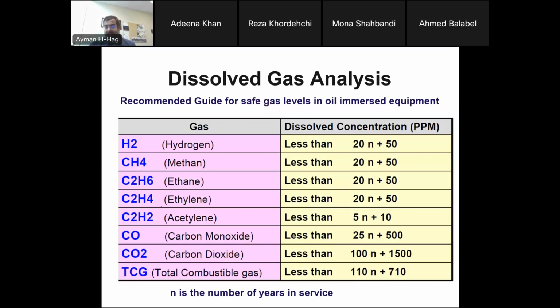And there is a recommended guide, again for all-age transformers, where N is the number of years in service. These are the gases we are looking for: H2, CH4 (methane), C2H6 (ethane), C2H4 (ethylene), C2H2 (acetylene), CO and CO2, and the total combustible gases. So these are some limits. For example, for H2 it's 20N plus 50, where N is the number of years in service. Let's say you have a 10-year-old transformer, so the recommended value is less than 20 times 10, which is 200, plus 50. So it should be less than 250 ppm.